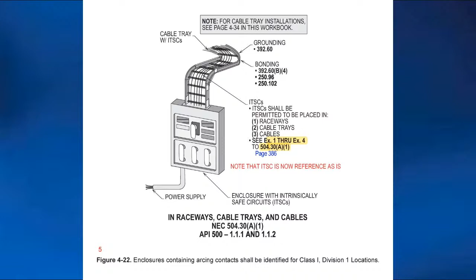What I can't really see is what the separation is. Does it give a measurement on that separation from the intrinsically safe circuit? Yeah, 2 inches. It's right here at this illustration, 504.30A as an example 2 on page 386. Notice you need a 2-inch separation, or you need the insulating non-metallic block that separates them.